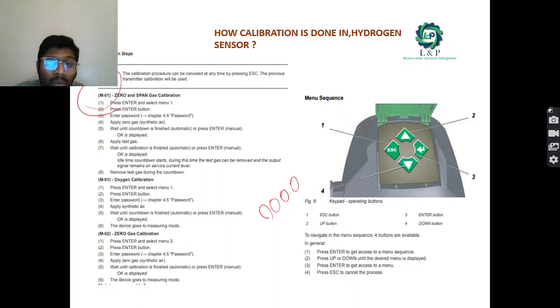Wait until the countdown is finished. Once it is finished, OK is displayed. Apply the test gas, and after applying the test gas, wait until the calibration is finished. Once it is done, OK will be displayed. There is an idle countdown time for everything. And once everything is done, please remove the test gas during the countdown.